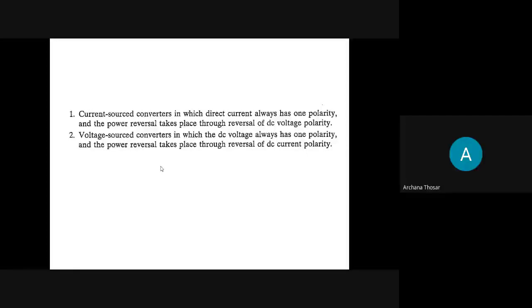In a voltage source converter, on the input side there is a capacitor, because it's a voltage source, so the voltage source has to be created. At the output side, you need an inductance. From 2-port network theory, you need an inductor at the output of the voltage source converter, and this inductance is provided by the transformer connected on the other side, or any reactance in the path. So the inductance requirement is automatically taken care of. Hence, the voltage source converter is always preferred over the current source converter.